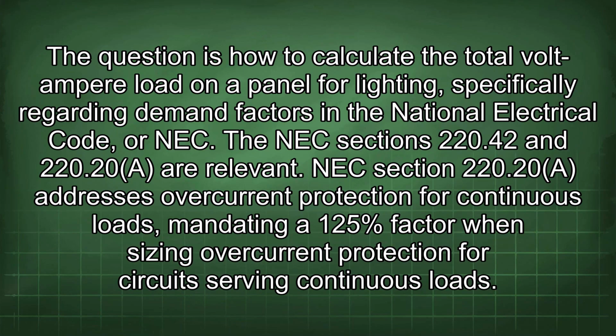The question is how to calculate the total volt-ampere load on a panel for lighting, specifically regarding demand factors in the National Electrical Code, or NEC. NEC sections 220.42 and 220.20 are relevant.